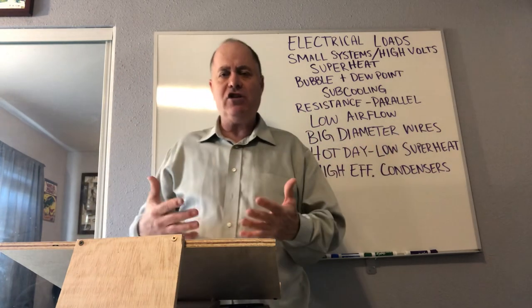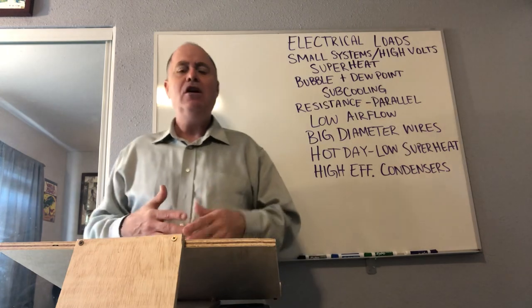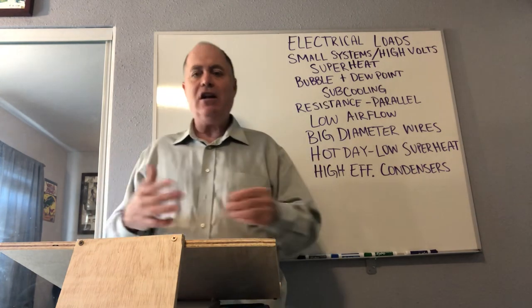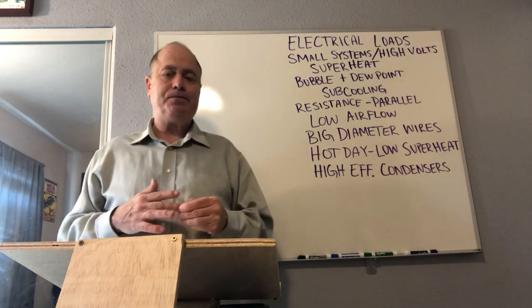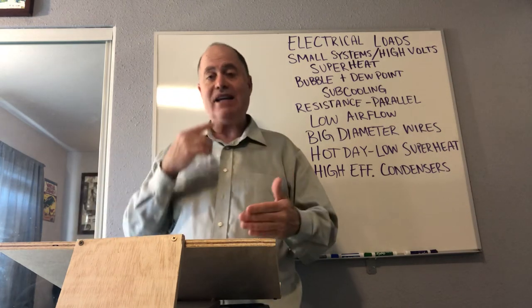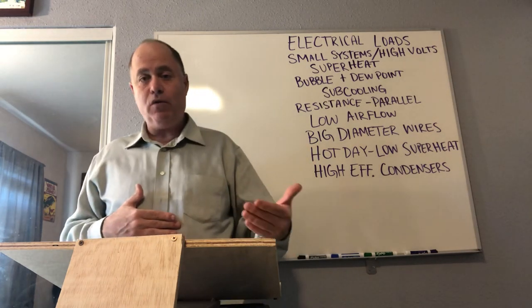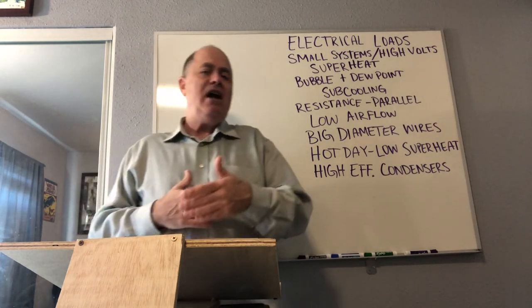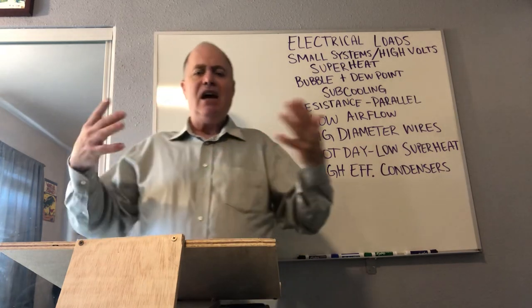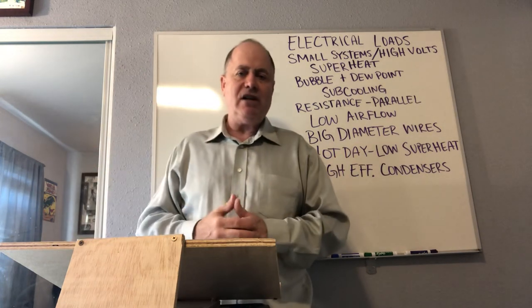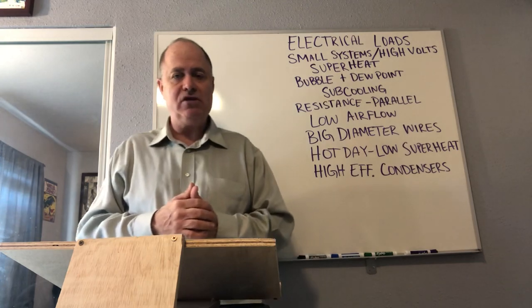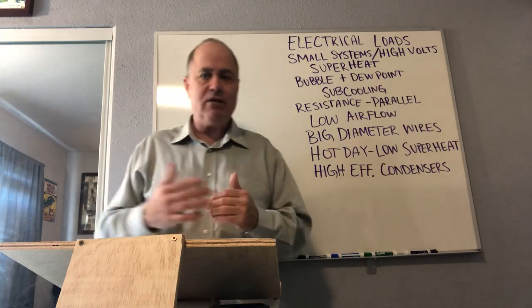Where something like a large air conditioning compressor requires a transformer and a contactor, the thermostats are low voltage — like 24 volts — and they barely pass maybe an amp or less, and they would energize a contactor to bring on the compressors indirectly.